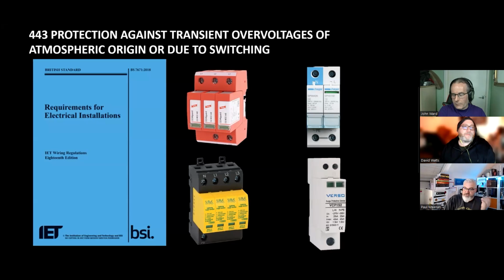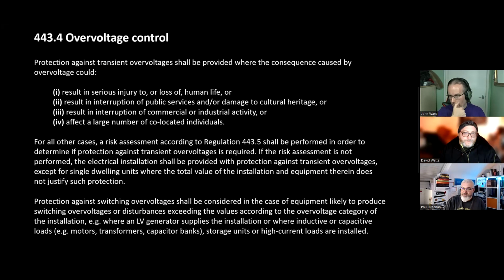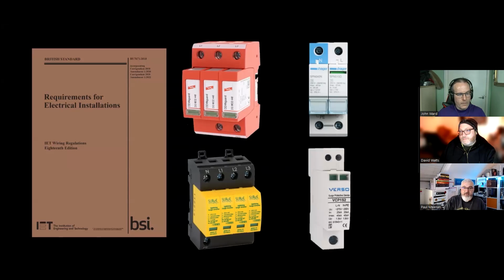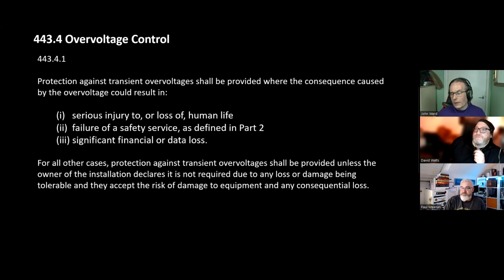Moving on, surge protection. It was chaos. There's various devices that we've all seen, some new to the market, some old, some on the value range, some on the expensive range, but there's a plethora of them. And we had this carnage of a regulation that caused a lot of arguments, and we had the calculated risk level, and nobody could understand it, and everybody wanted to get out of it. To be honest with you, it was frankly an embarrassing set of behaviours from the industry because of a poorly worded reg. Let's fast forward to the new Big Brown Book, and there we go. Far simpler. The risk assessment is gone.